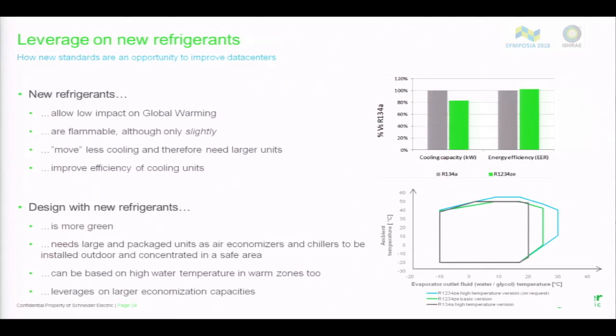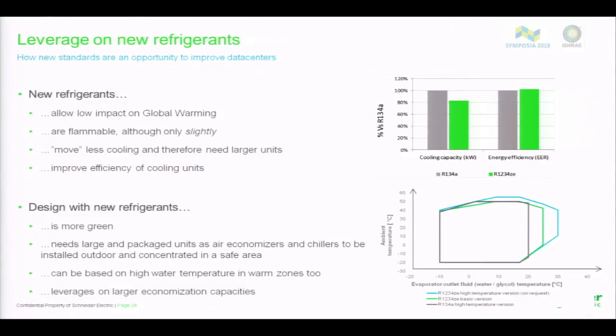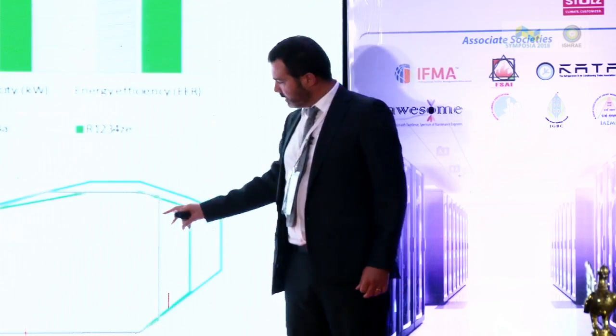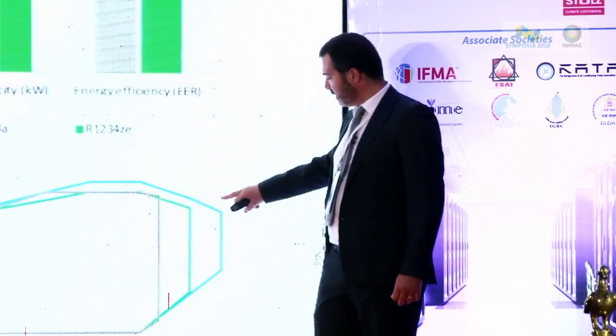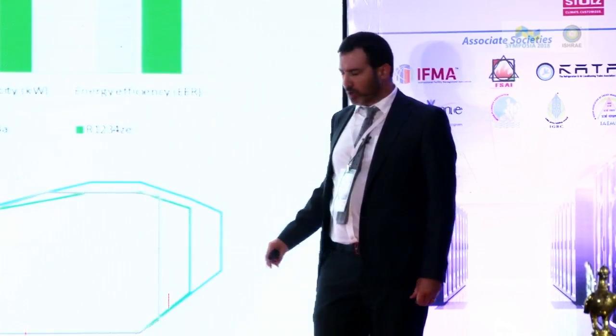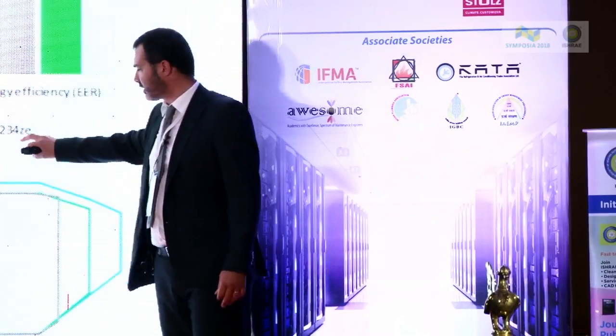the gray one is the operating envelope of a normal chiller with 134A. The green one is a typical data center chiller. The blue line is the same with this new refrigerant.